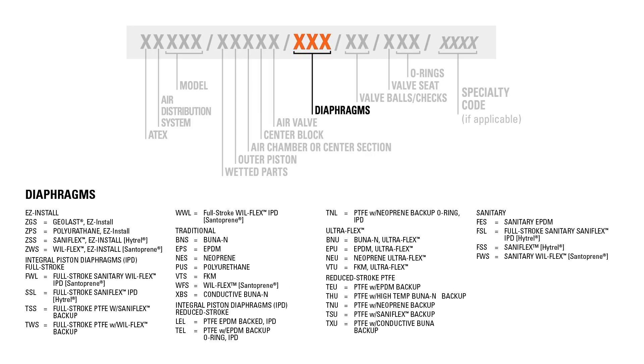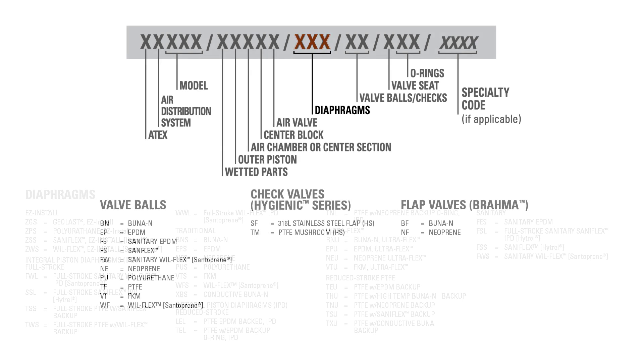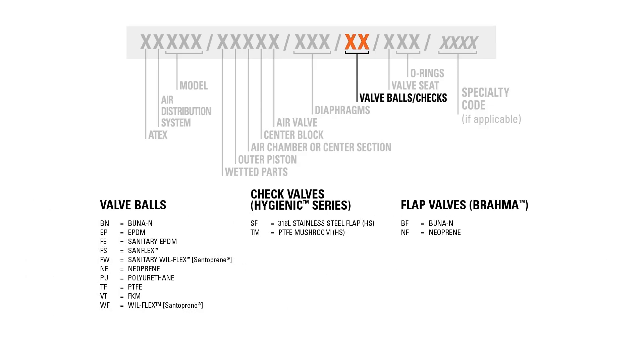The third section of a Wilden AODD pump's model designation denotes the style and material for the diaphragms. Each three-digit combination of letters identifies a specific diaphragm style and material. The fourth section of the model designation denotes the check balls. In the case of the hygienic or Brahma series, this section identifies the material of the flap or mushroom valves used in place of the check balls.